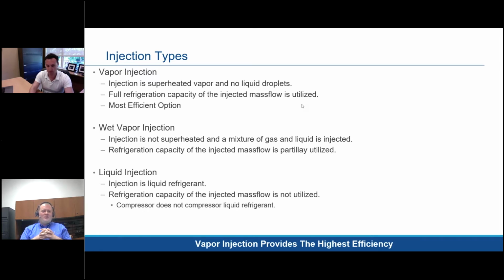Liquid injection is another option. One of the benefits of liquid injection is it's simple to use. You don't need the economizer, which is the heat exchanger. But one of the downfalls is you don't get the extra capacity using liquid injection, because you're not adding that vapor to the scrolls to get that increased mass flow. But it does a good job at cooling and allowing you to operate at those extreme high compression ratio conditions, and it's a little bit more of a simpler offering as well. I'll have a slide coming up to go over those differences as well.